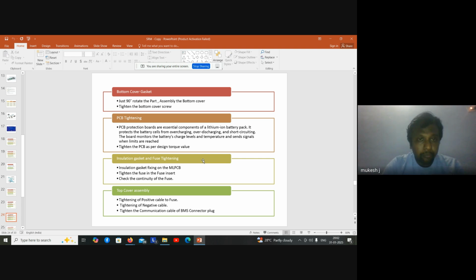And the protection circuit board is one of the major parts in the lithium ion battery. It will protect that battery from overcharging, over discharging and short circuit. The board monitors the battery level of charging, the temperature and the signal. Once it reaches the limit, it will give that indication to the BMS system, and to safeguard that battery, next tighten that BMS board.